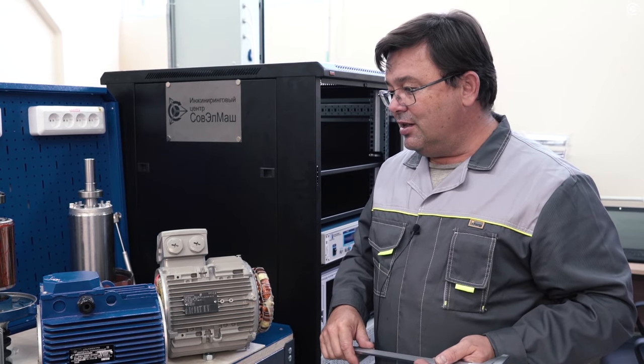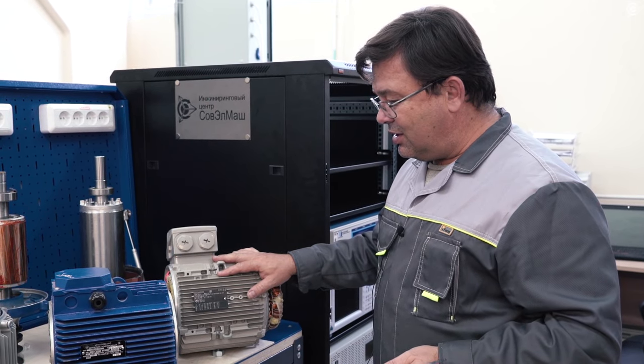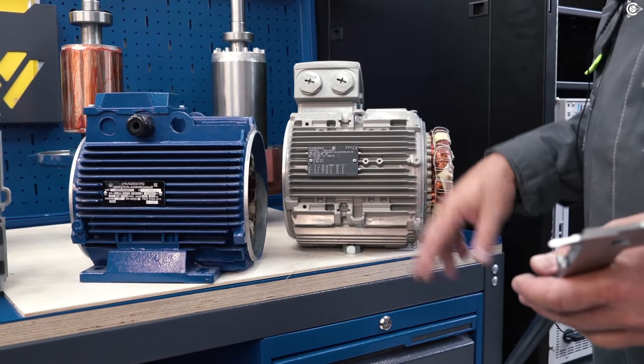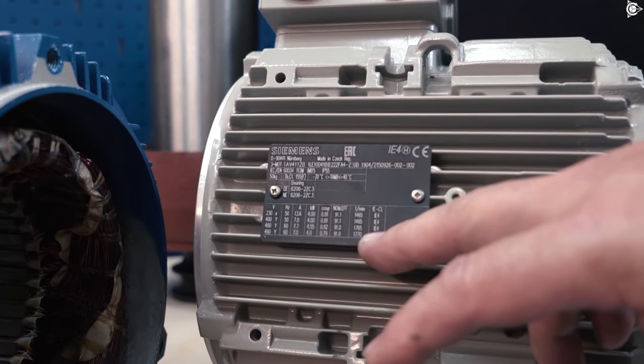We are in the laboratory of SovElMash, and I would like to show you the difference between class IE4 electric motors and standard induction motors with classic winding. We have one electric motor of the energy-efficient class IE4. You can see it here on the nameplate — class IE4 for various voltage and frequency.